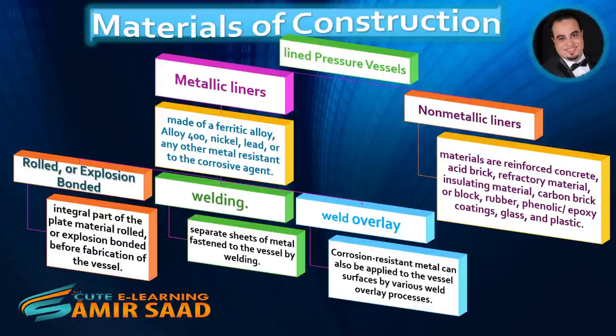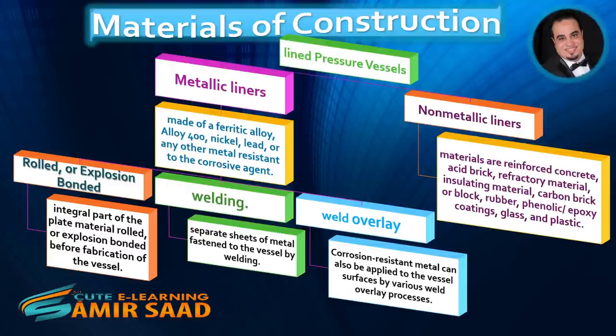Metallic liners may be made of a ferritic alloy, Alloy 400, nickel, lead, or any other metal resistant to the corrosive agent. Metallic liners are installed in various ways: first, rolled or explosion bonded as an integral part of the plate material before fabrication of the vessel; second, welding — separate sheets of metal fastened to the vessel by welding; third, weld overlay — corrosion resistant metal applied to the vessel surfaces by various weld overlay processes.